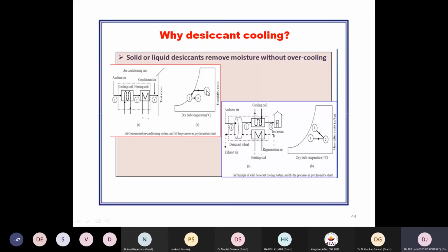The same operations, by state points 1, 2, and 3, can be explained on the psychrometric chart. Now our desiccant cooling. In desiccant cooling, you see that a cooling coil may be used, but that cooling coil is not necessarily only VCR, only a contact type evaporator; it can be a non-contact evaporator. There may be diversified options and applications according to the need and requirement. If humidity and temperature are required to be very low or fast, then you may go for mechanical cooling. Otherwise, ordinary cooling will play its role to sustain a given temperature range.